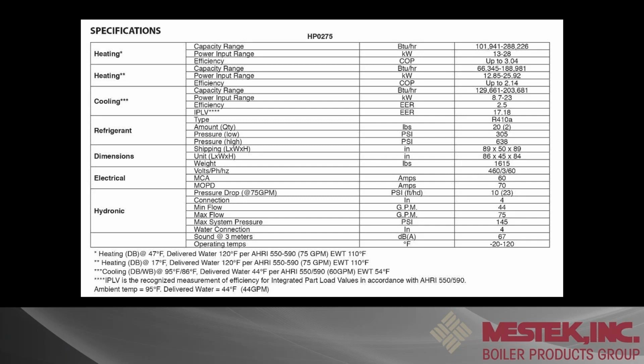But that being said, I just want to get into our minimum flow and our maximum flow. Because it is an inverter compressor, we can ramp the flow rate down, and we can also ramp the flow rate up. So our minimum flow would be 44 GPM. Our maximum flow would be 75 GPM per unit.